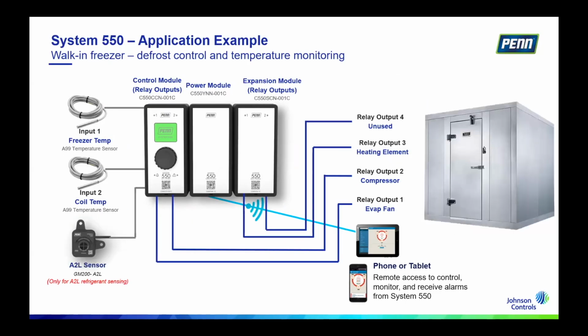The last one here is a more complicated application. Here, in addition to monitoring the freezer temperature and the evaporator coil temperature, we're also now adding an A2L sensor, a refrigerant sensor. And so what's going to happen here is if there is a leak, or for whatever reason if the sensor is faulty, the user will select the mitigation protocol.